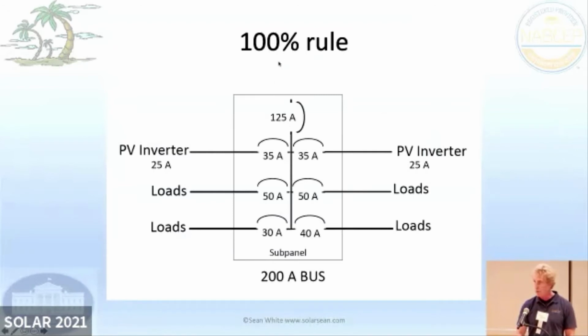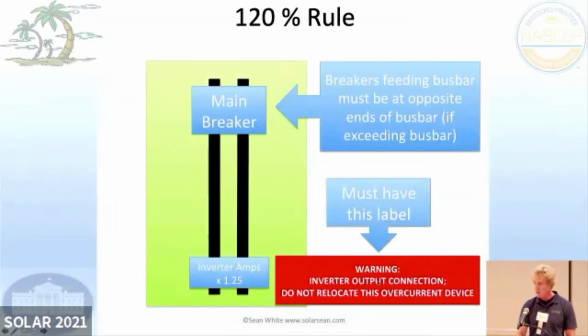100% rule. So this is not the 120% rule, but the reason is the 120% rule, we'll skip ahead, has to have this little sticker here that says, do not relocate this overcurrent device. The 120% rule is like, you have to be on the opposite end of the bus bar from your main breaker. You've got to be on opposite ends. And that's so you don't overload that bus bar. So solar's feeding it from one side, the main breaker is feeding it from the other side. And so that's why we have the 120% rule like that.